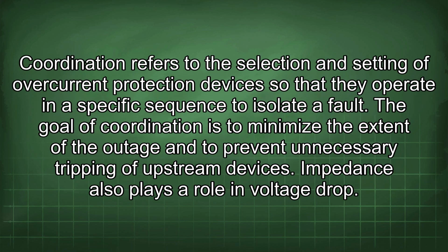Coordination refers to the selection and setting of overcurrent protection devices so that they operate in a specific sequence to isolate a fault. The goal of coordination is to minimize the extent of the outage and to prevent unnecessary tripping of upstream devices. Impedance also plays a role in voltage drop.